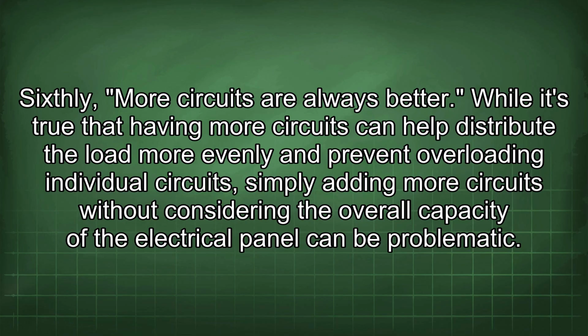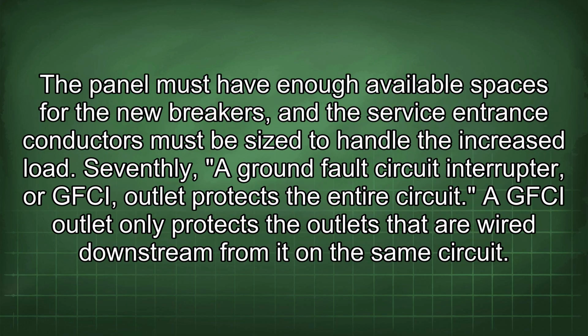Sixthly, more circuits are always better. While it's true that having more circuits can help distribute the load more evenly and prevent overloading individual circuits, simply adding more circuits without considering the overall capacity of the electrical panel can be problematic. The panel must have enough available spaces for the new breakers, and the service entrance conductors must be sized to handle the increased load.